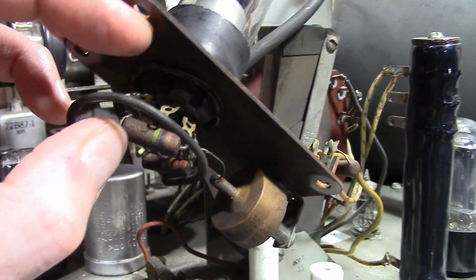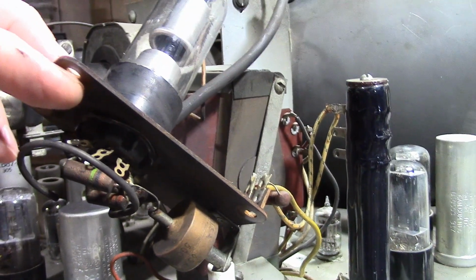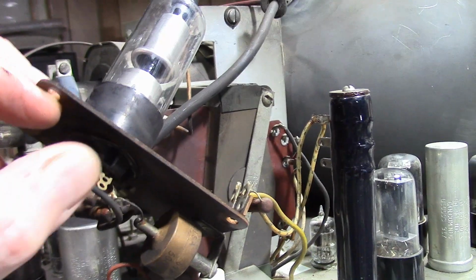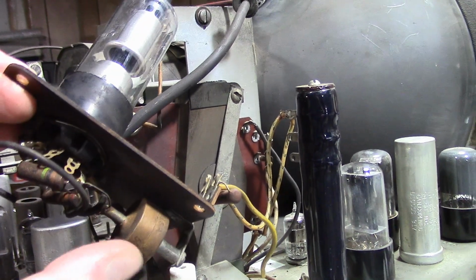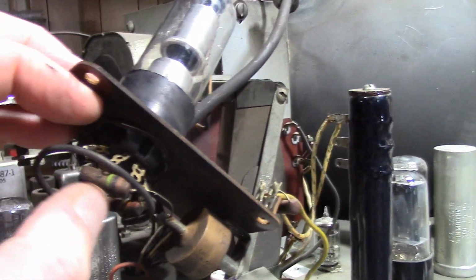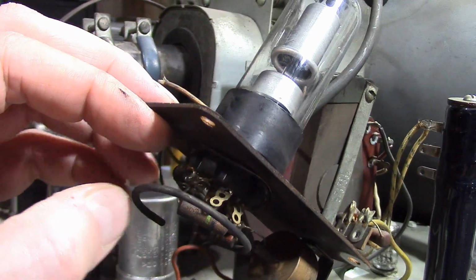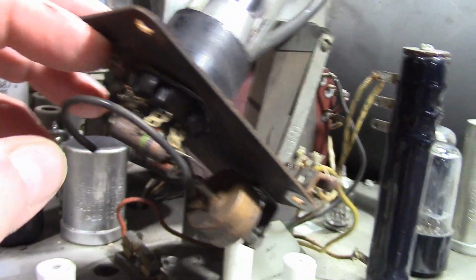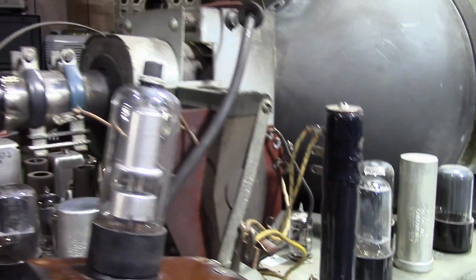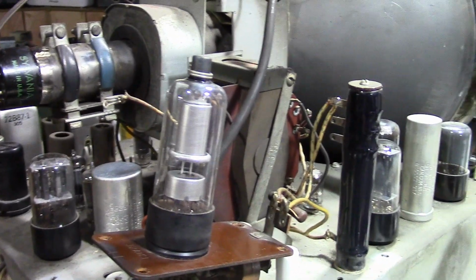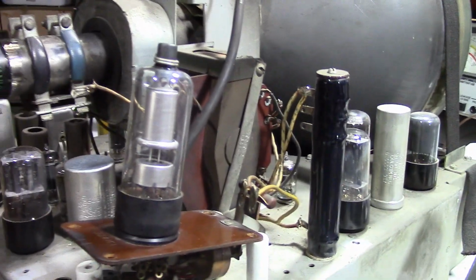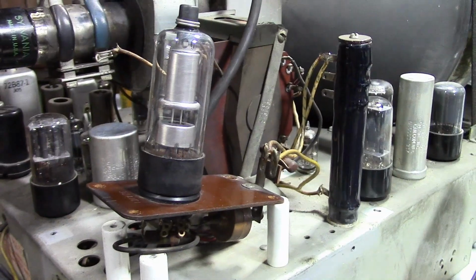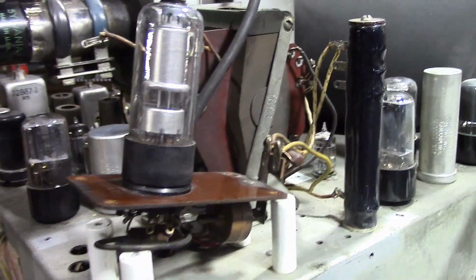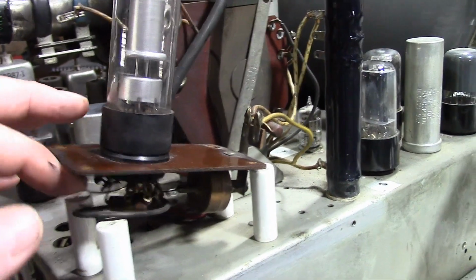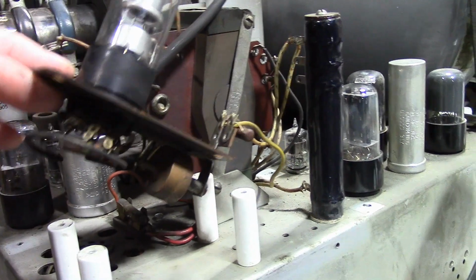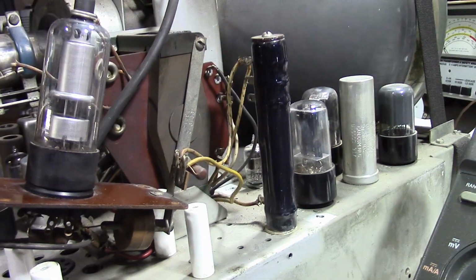Now this guy is something you definitely want to check. That is in series with the high voltage lead, so got the rectifier tube, filter cap, and then this resistor going over to an unused lug, and that's with a high voltage lead. It's a 1 meg resistor in there to, I guess, limit the current. There's very little current going through it, even with a 1 mega ohm resistor in series with it. It really doesn't affect the voltage much. These can drift high, which will then definitely affect your high voltage output.